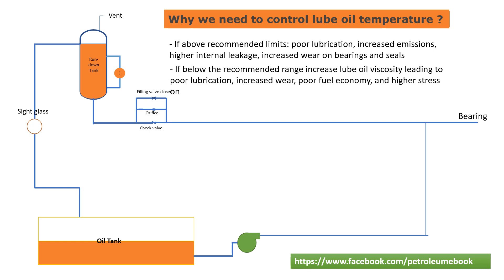Temperatures below the recommended range increase lube oil viscosity, leading to poor lubrication, increased wear, poor fuel economy, and higher stress on pumps, valves, fittings, seals, and other components.